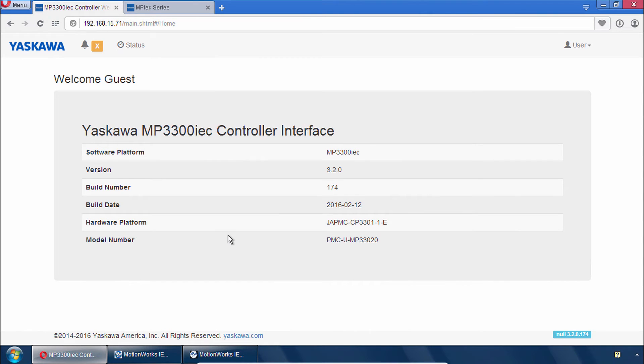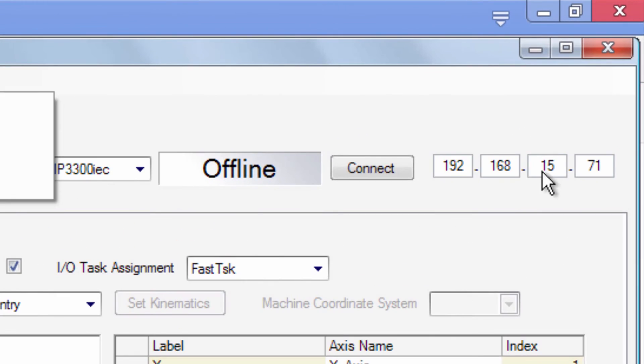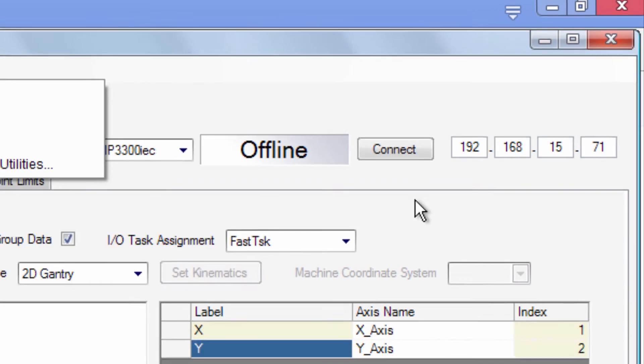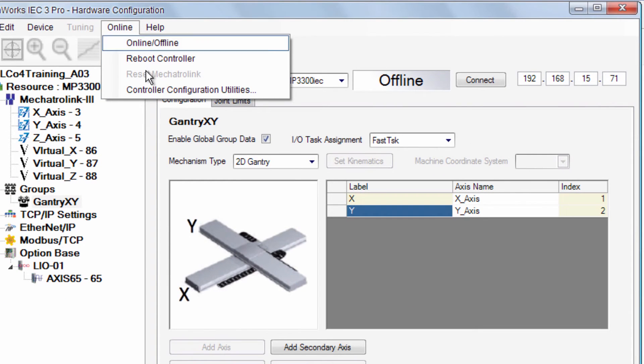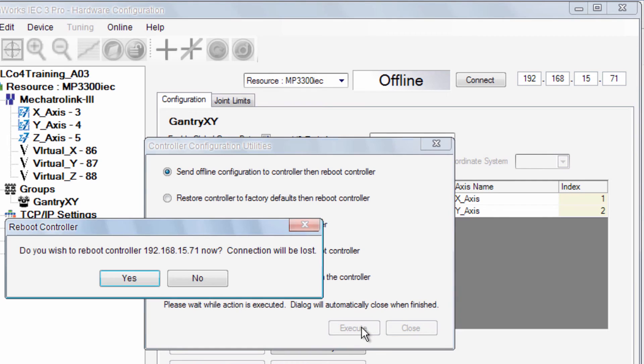And first we'll need to go to the hardware configuration and send this configuration to the controller. Check your IP address. Go to the online menu controller configuration utilities and choose send offline configuration and execute. You do have to reboot the controller.